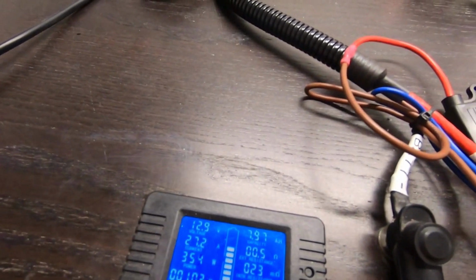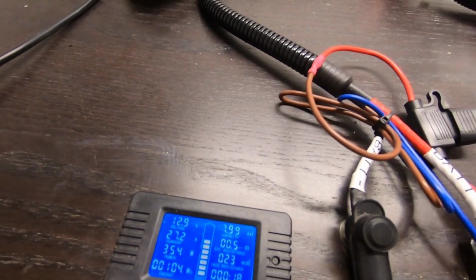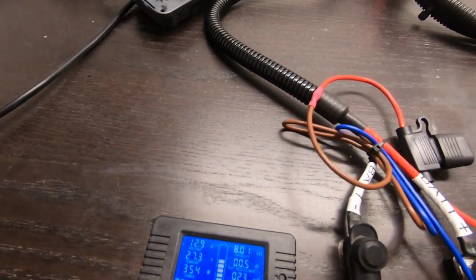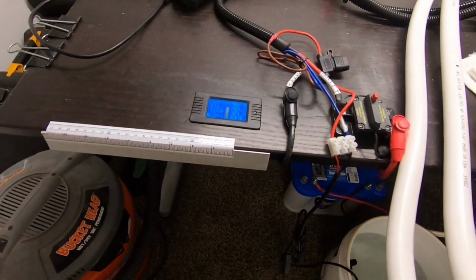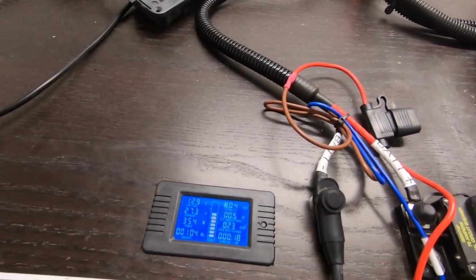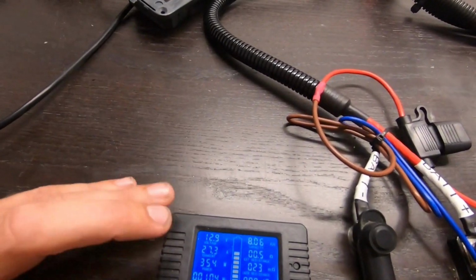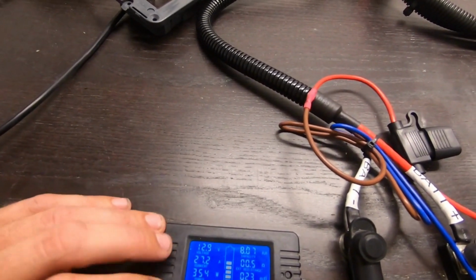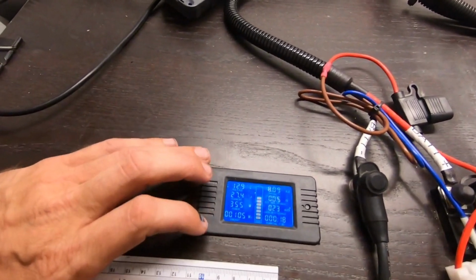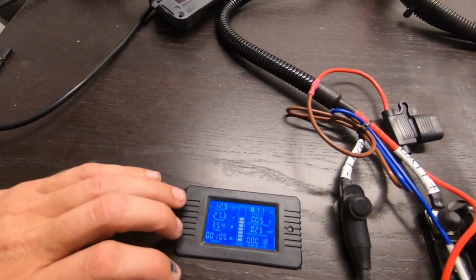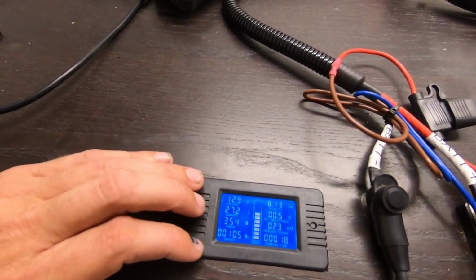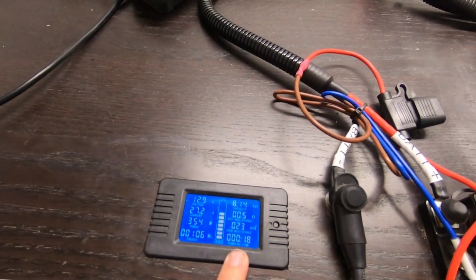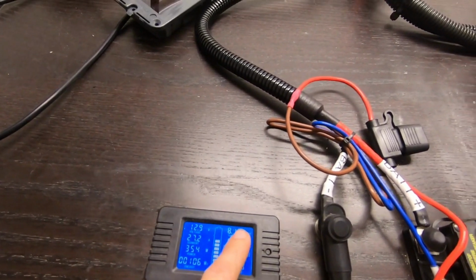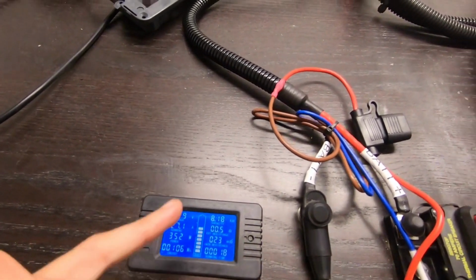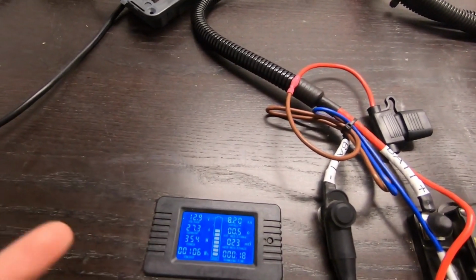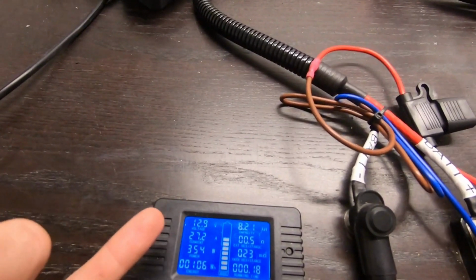I'm going to keep this unit running, I'll check it in the morning. By that point, the BMS will have kicked in and turned off the unit, which will stop this meter. So once we turn the battery back on, or reset the BMS, it'll allow us to see what kind of time it ran for, how many amp hours we got out of the battery, and what the voltage is at, but we're going to see it in the high 11s.